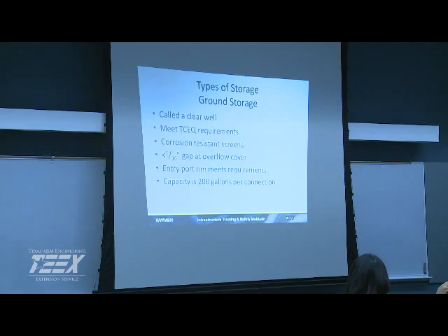And then the EPA rule is 200 gallons per connection for your capacity. And I know we've been talking about in the state, y'all are talking about, what, 24-hour capacity? So if you got a 10 MGD system, you got to have 10 MGD available. What we do is we give out our average pumpage for you. Okay. And then average all that together. That's their capacity. It's not their design capacity. Right. We also have what their operational history is. Mm-hmm. And we look at that and see what they have around with the storage.